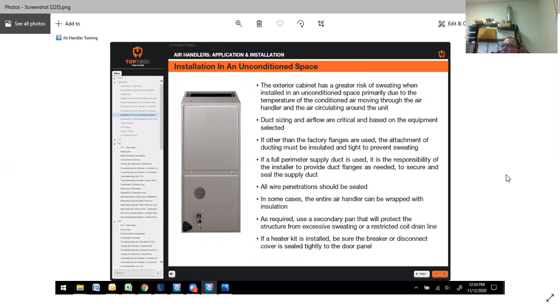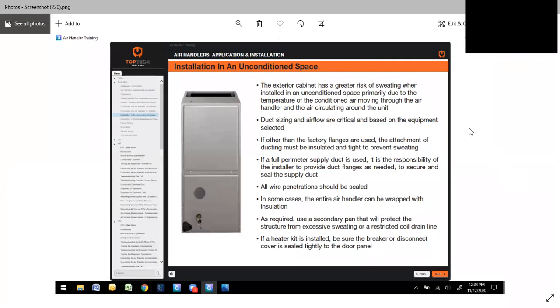When you're installing a unit in an unconditioned space, be it a crawl space or attic, there's a few provisions for that. The exterior cabinet has a greater risk of sweating when installed in an unconditioned space, primarily due to temperature moving through the air handler and the air circulating around the unit. Duct sizing and airflow are critical and based on the equipment selected. If other than factory flanges are used, the attachment of ducting must be insulated to prevent sweating.